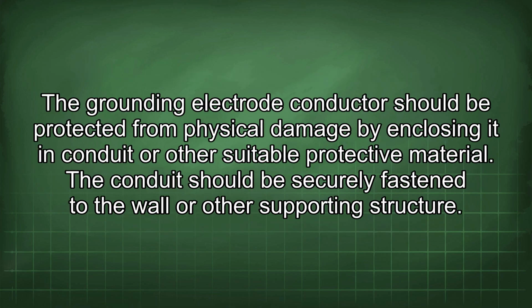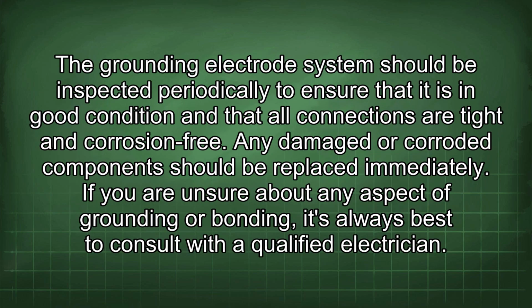The grounding electrode conductor should be protected from physical damage by enclosing it in conduit or other suitable protective material. The conduit should be securely fastened to the wall or other supporting structure. The grounding electrode system should be inspected periodically to ensure that it is in good condition and that all connections are tight and corrosion-free. Any damaged or corroded components should be replaced immediately.